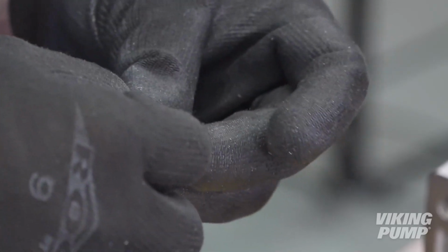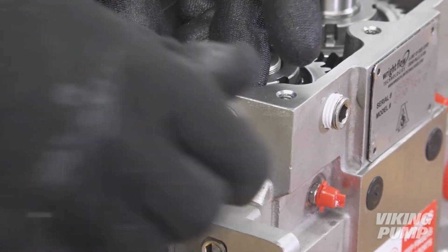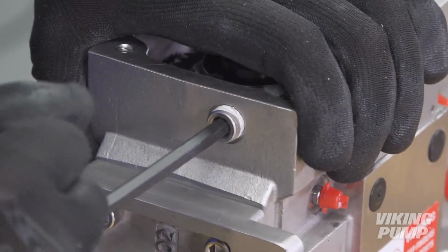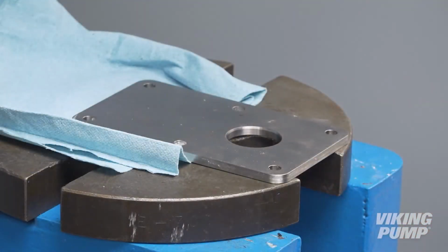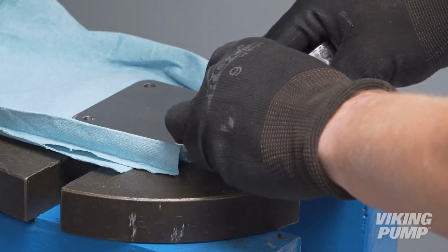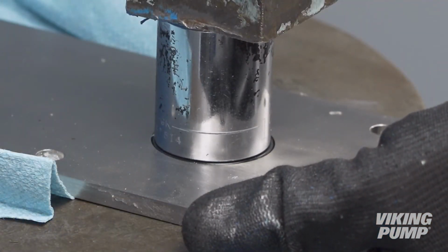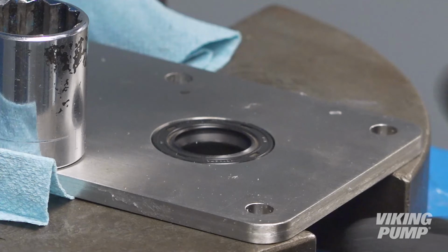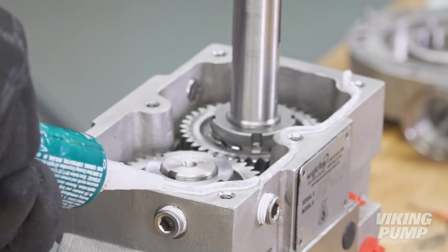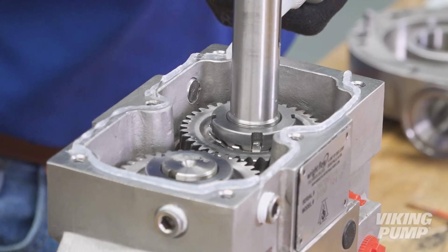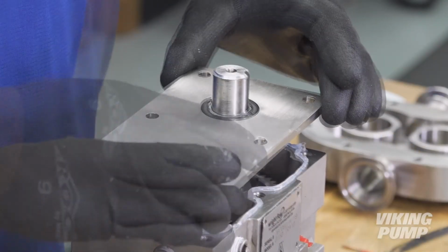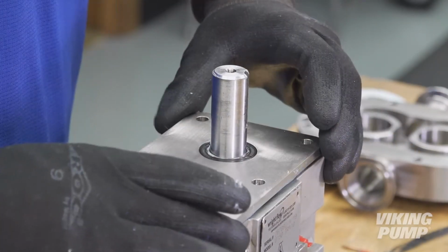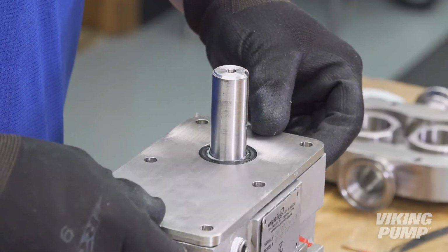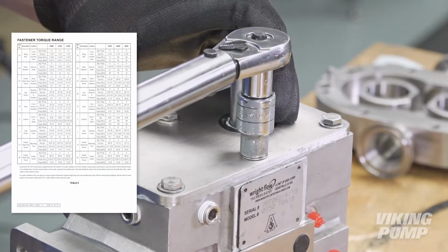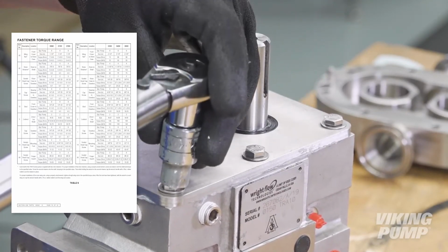Next, replace the drain plug. Wrap PTFE tape around the plug threads and install. Press a new lip seal into the gearbox cover with the lip facing outward. Apply a continuous bead of silicone sealant around the gear case, following along the inboard side of each bolt hole. Secure the gearbox cover. The shaft key may be taped over to protect the gearbox cover lip seal. Torque the cap screws to the appropriate torque value. This can be found in the technical service manual.